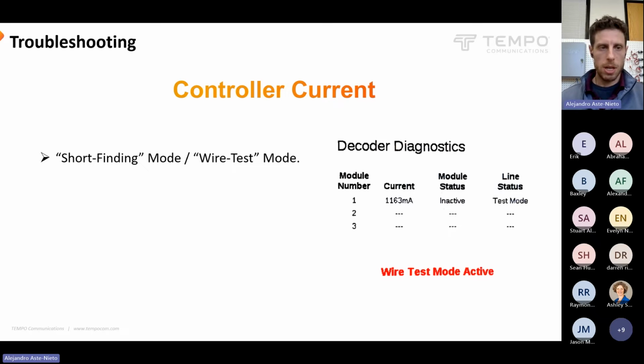So, like I mentioned, a lot of controllers will have a short finding or wire test mode, and they'll be able to display how much current is going out there on a particular wire path. And some of the other older or less sophisticated controllers might not go into this mode. They might just shut down, and that might be the only clue that you have that there's an overcurrent happening. It might shut down, might blow a fuse.